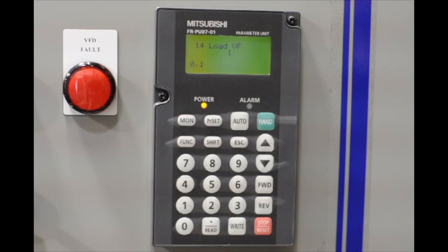There's two settings for this parameter. Zero is for constant torque, and one is for variable torque. If this is a pump or a light-duty fan, you can leave it at one for a variable torque setting.